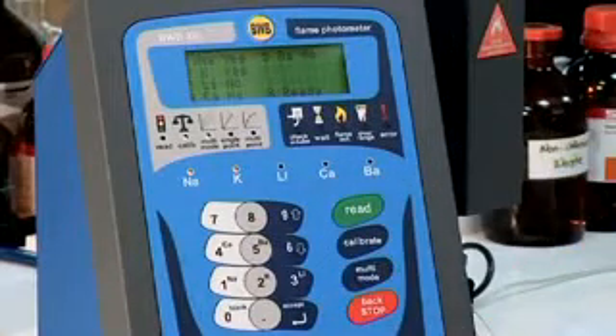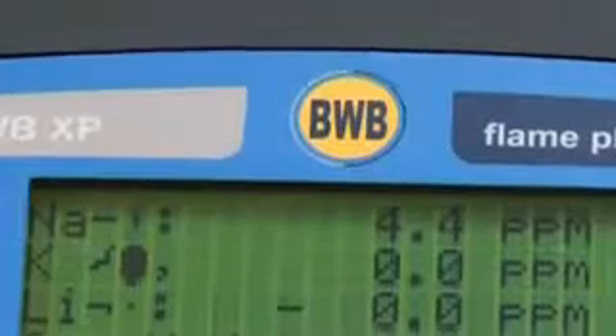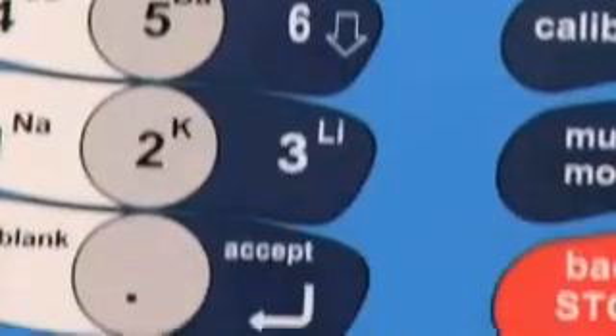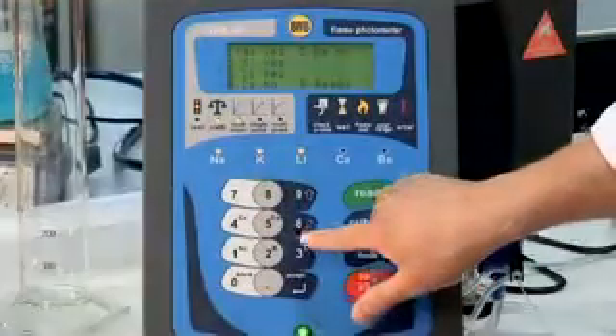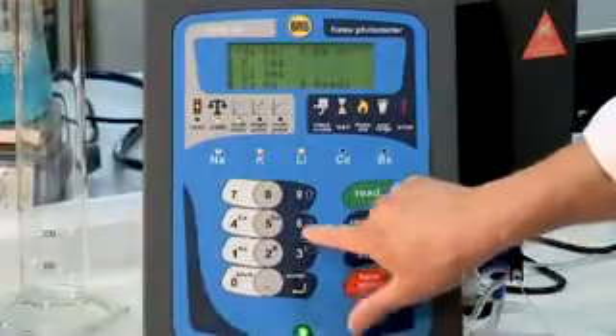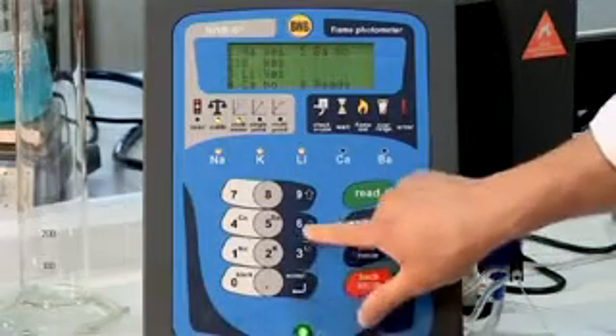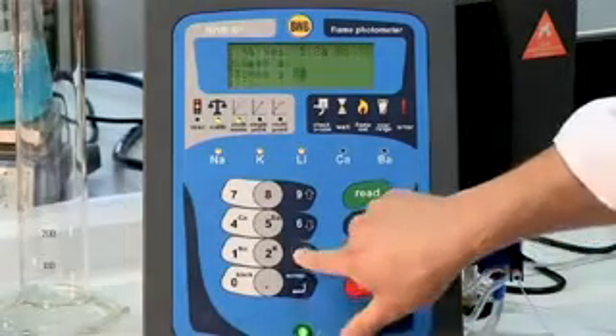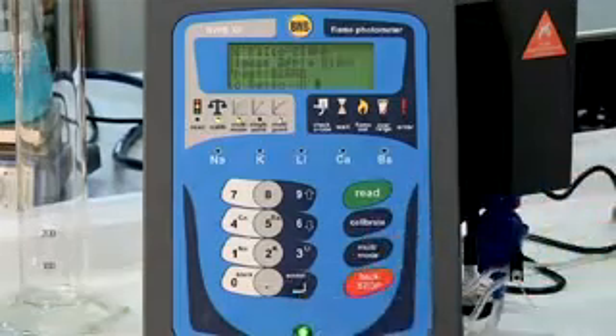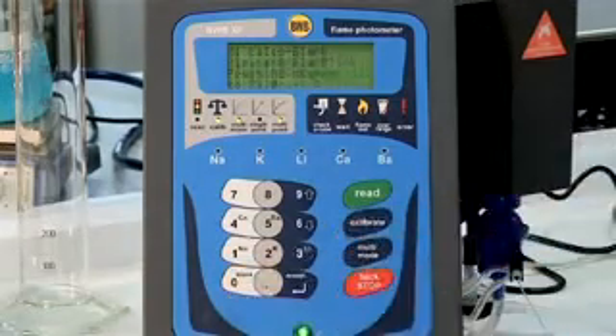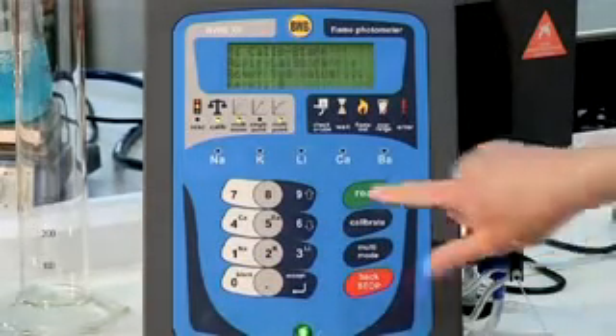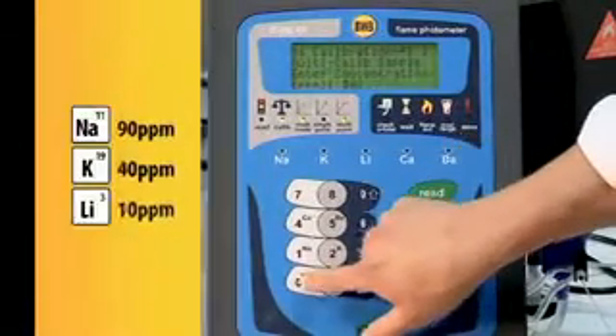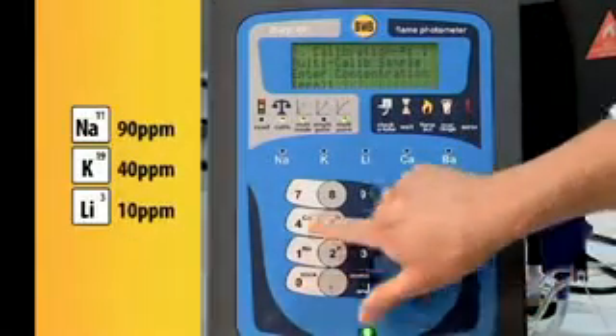From the main menu we can go through the calibrations menu and to the calibrate ions menu, where we will opt for number 8, multi, or we can press the multi-mode key and go to the same location directly. For each ion, pressing its respective key will toggle between yes and no. Yes, it will be included in the calibration. No, it will not be included. The up and down keys can also be used to toggle between yes and no. In this calibration, we toggle to yes for sodium, potassium and lithium.